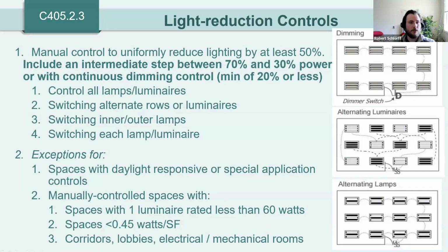Light reduction controls, there have not been significant updates to this section within this code cycle. But this is essentially lighting reduction controls for all other spaces that we didn't previously cover and that are not covered by other specific sections. The intermediate step listed under that first point: manual control to uniformly reduce lighting by at least 50%, but must include an intermediate step between 70 and 30% power, or use continuous dimming control, again with a minimum set point of 20%. So that intermediate step is the new requirement here.